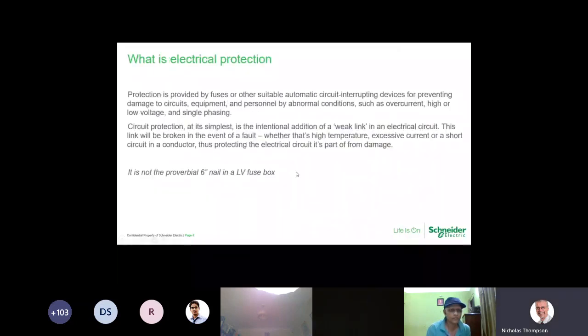Protection, electrical protection. We take protection for granted in every aspect of our lives, and electrical protection is nothing new. We're all used to the 13 amp fuse that goes into the plug. How often those blow, I really don't know. I can't ever remember changing a fuse in the last 5 years because it's blown. Things are becoming a lot more reliable and a lot more safe. When we look at overall protection within our own homes, we have a series of MCBs, or if it's a really old distribution board, we've got fuse wire.